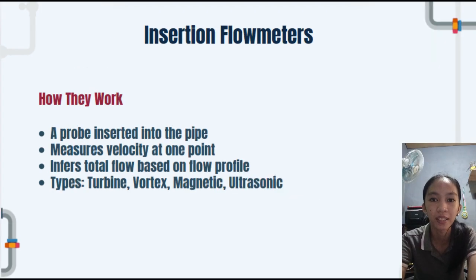Now, let's move to our second method, insertion flow meters. If change of quantity works from the outside, this method works from the inside, but only at a single point. The concept here is that a probe is inserted into the pipe through a single tap. This probe measures the fluid velocity right at its tip. Since we can't measure the velocity everywhere at once, we use our knowledge of fluid dynamics to infer the total flow rate based on its single point measurement. There are several types like insertion turbine, vortex, magnetic, and ultrasonic, each with their own sensing principle.